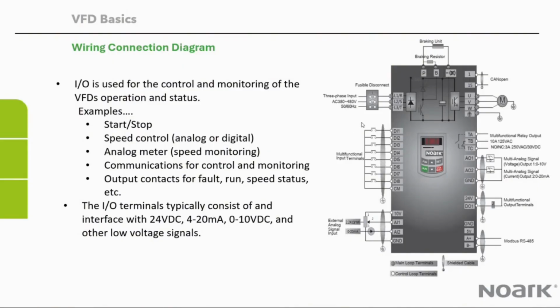We've got all the digital inputs that are used to start, stop, maybe do preset speeds. I want to run at this speed and that speed, and I change those inputs. You just program them accordingly. And various other functions are done with the digital inputs.